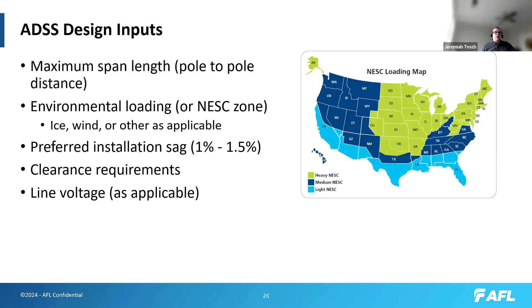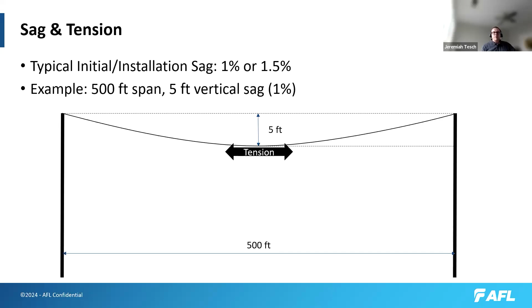So this is a 500-foot span scenario. So typically your installation sag will be 1 to 1.5%. So at a base level, you have that certain amount of sag. So for the 500 foot and say a 1% installation sag, it would sag 5 feet from the horizontal line. And then if there's any additional weather loading, environmental loading, it could sag even further down. Maybe some ice here would pull it straight down, or a crosswind would push it sideways.